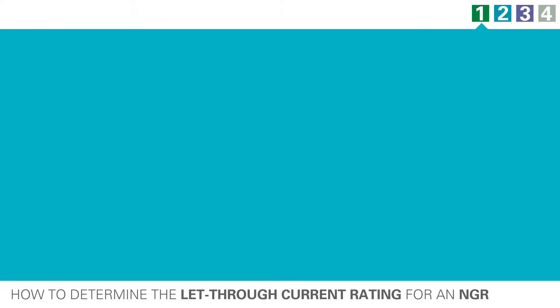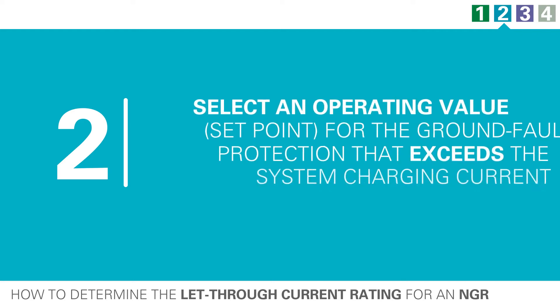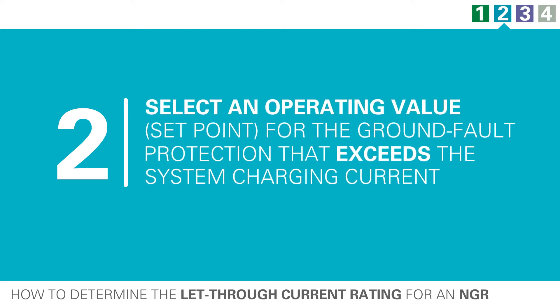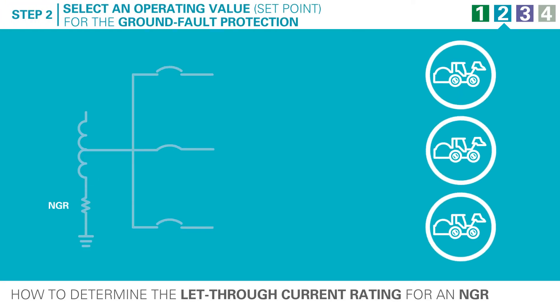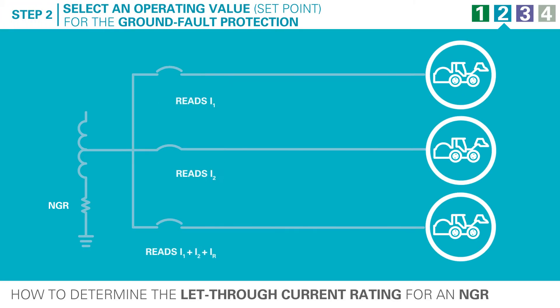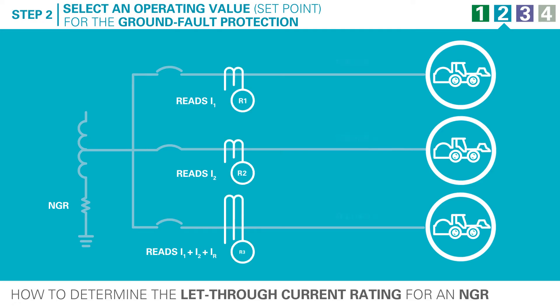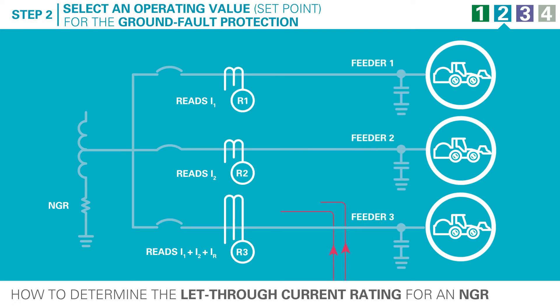Step two in determining the let-through current is to select an operating value or set point for the ground fault protection that exceeds the system charging current. If the operating value of a ground fault relay is less than the charging current of the feeder it is protecting, it will cause a nuisance trip.